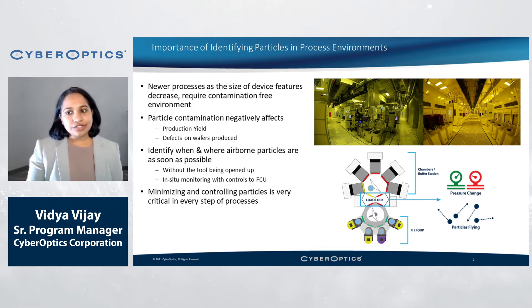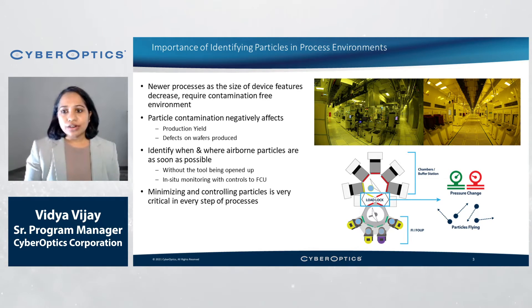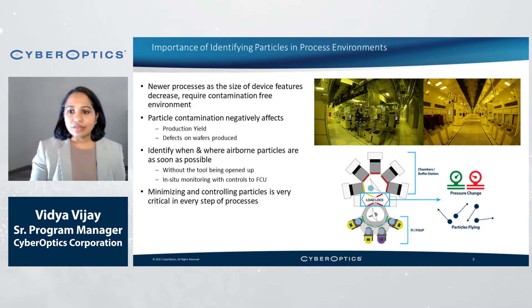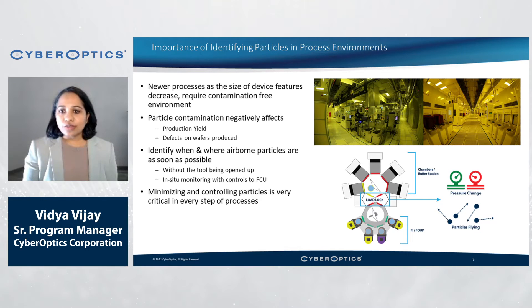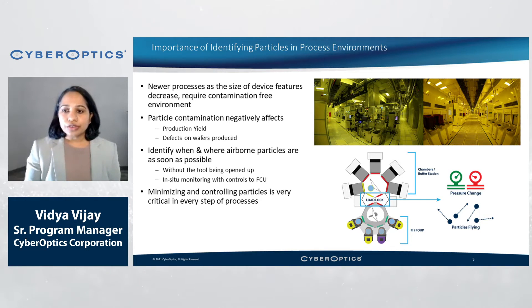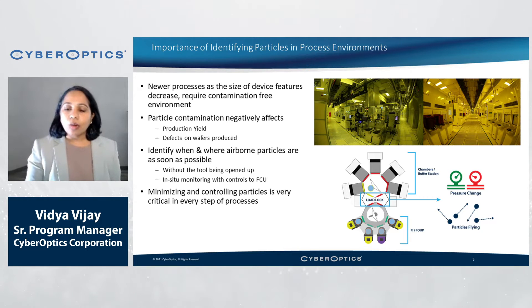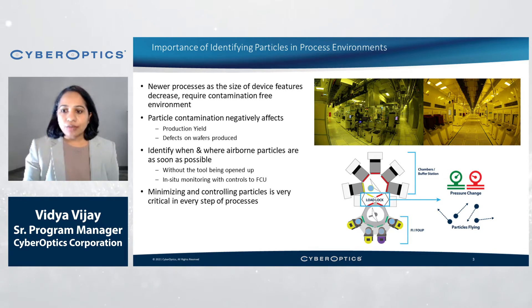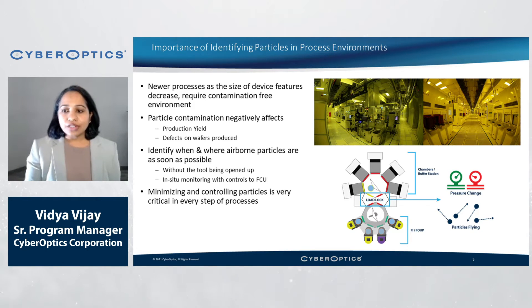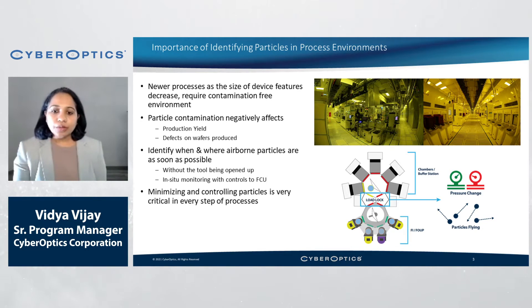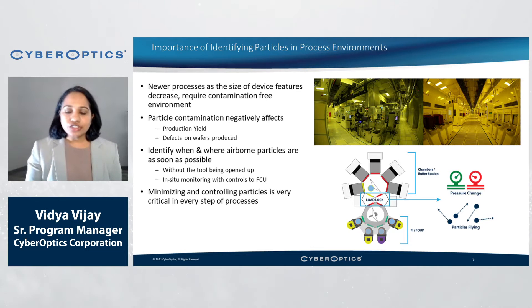Fine particles less than 5 micrometers in diameter are almost everywhere in the atmosphere, but they do not significantly affect standard industrial processes. The general use of HEPA filters removes almost all particulates from the makeup air within the clean room. However, in semiconductor manufacturing, operations involve a very special environment where particles and organic vapors can be produced during certain processes and can cause serious contamination, affecting loss of yield and defects in wafers produced. Quickly identifying when and where airborne particles originate, as well as the source of contamination, proves very challenging. Minimizing particles in semiconductor fab environments remains a critical success factor.